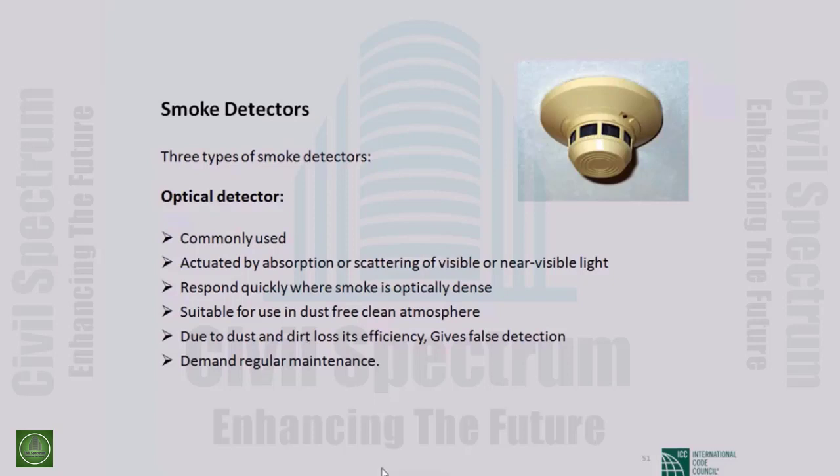Or sometimes, due to dust deposition in our country, there is always some false alarm. Sometimes it is equipped with a special tube to avoid this, but it is prone to false alarms. It is prone to giving a wrong indication.